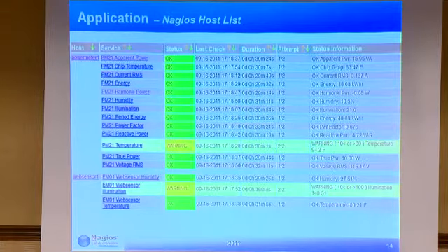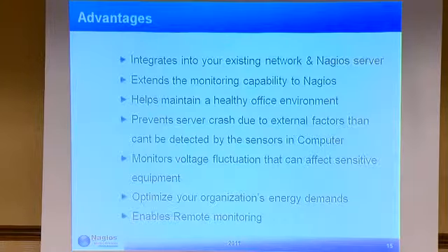And you can see the warning alerts also displayed, and this is how the warning is also shown. We have a temperature warning here, which is around 94 Fahrenheit. Probably the cooling system is not working so well, or that part of the room is pretty hot.